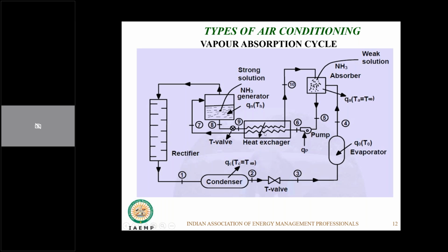When it comes into the absorber, a weak solution of water is coming in. When I say weak solution, weak in the sense of the concentration of ammonia present in it. As it comes over here, this weak ammonia water solution absorbs the vapor coming in from the evaporator. As it starts absorbing the vapor, it becomes a strong solution, and this strong solution is pumped through a heat exchanger. Then heat is added over here.